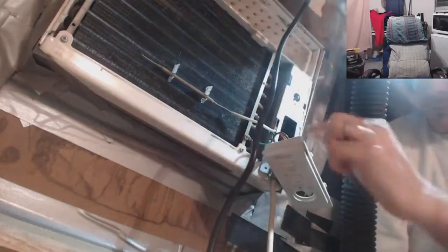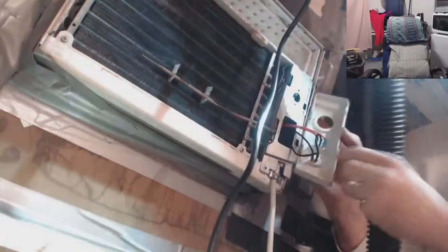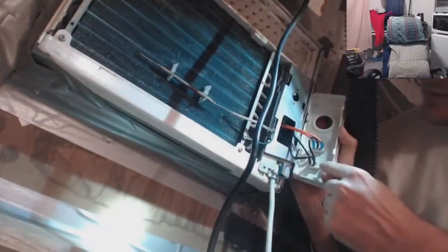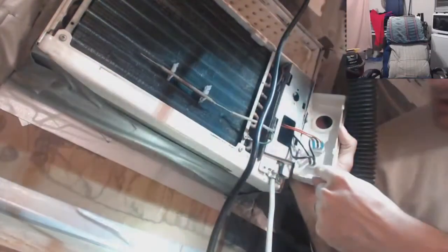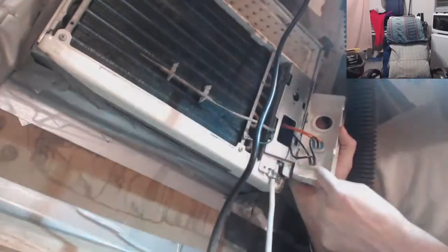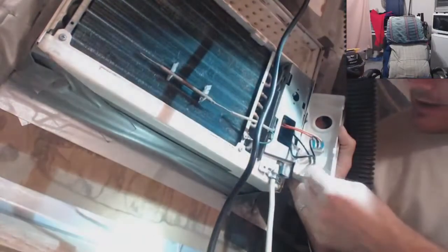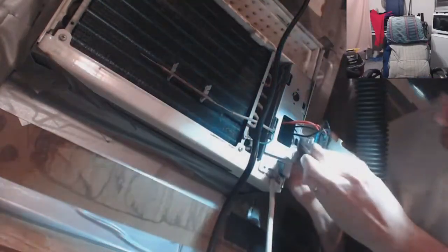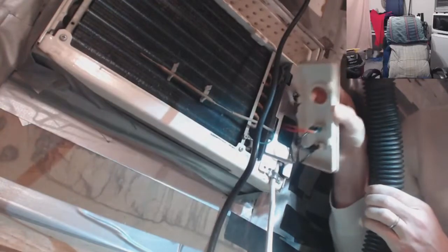I just touched bare metal at the bottoms of these switches. You can see these are just like two plugs plugging into either side of the power switch here. And there's a little bit of metal exposed on the bottom of each, so I put my probes on the exposed metal and I set it to AC and it marked 120 volts. So these are live. There's actually water in this thing. That shouldn't be there.